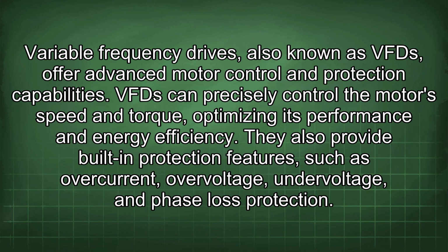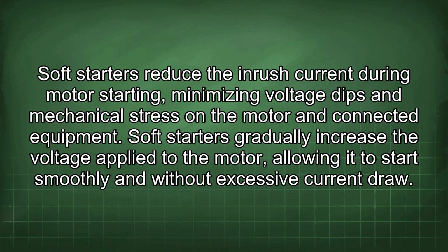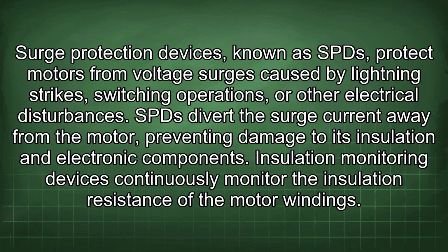Variable frequency drives, also known as VFD, offer advanced motor control and protection capabilities. VFD can precisely control the motor's speed and torque, optimizing its performance and energy efficiency. They also provide built-in protection features such as overcurrent, overvoltage, undervoltage, and phase loss protection. Soft starters reduce the inrush current during motor starting, minimizing voltage dips and mechanical stress in the motor and connected equipment. Soft starters gradually increase the voltage applied to the motor, allowing it to start smoothly and without excessive current draw. Surge protection devices, known as SPD, protect motors from voltage surges caused by lightning strikes, switching operations, or other electrical disturbances. SPD divert the surge current away from the motor, preventing damage to its insulation and electronic components.